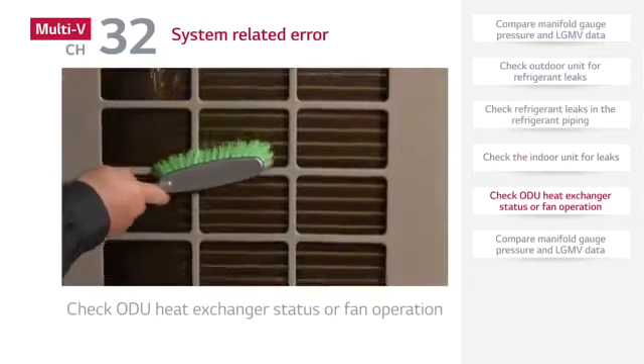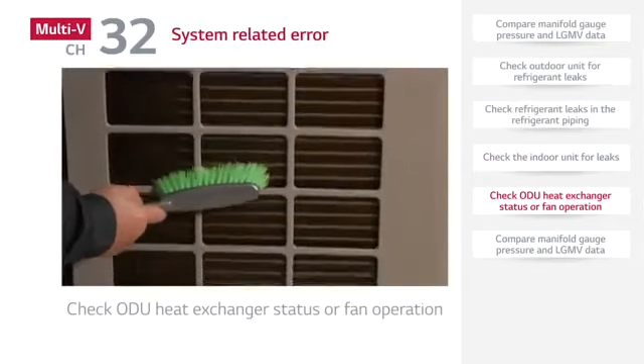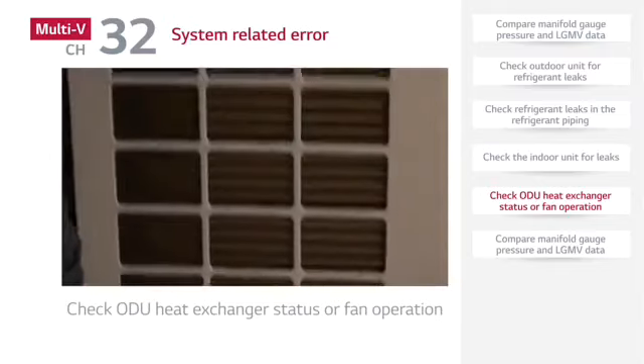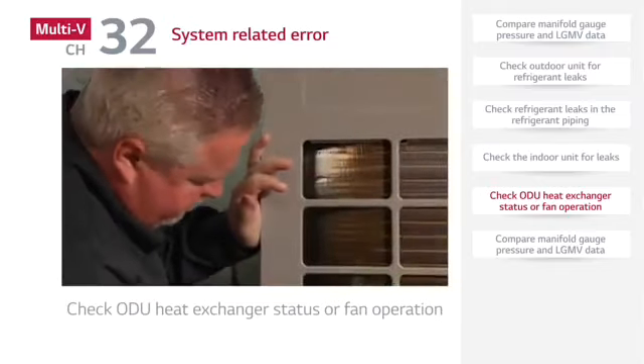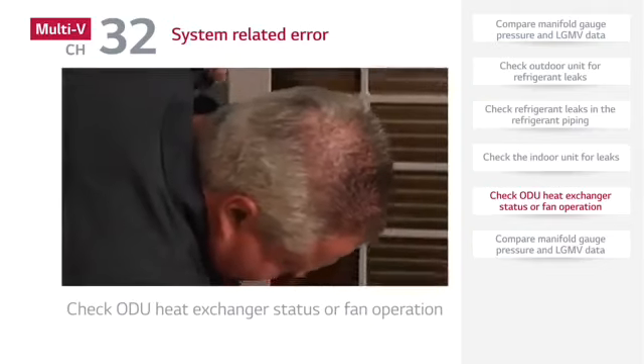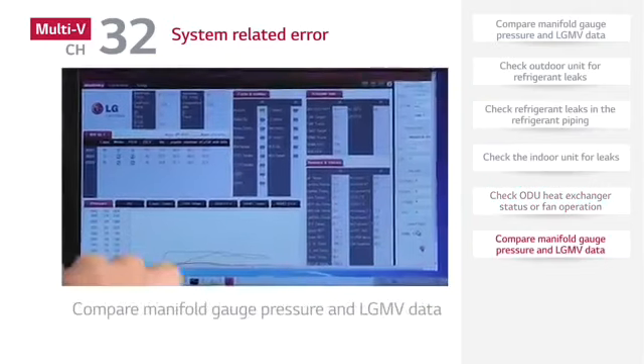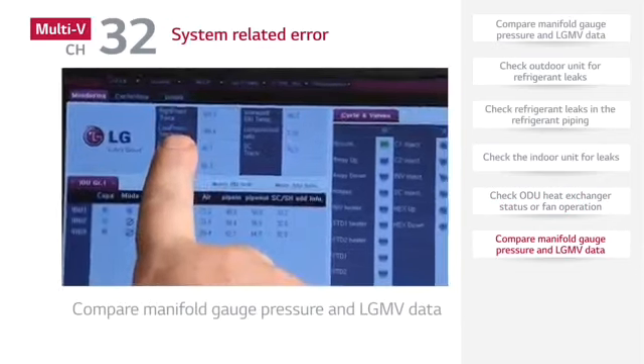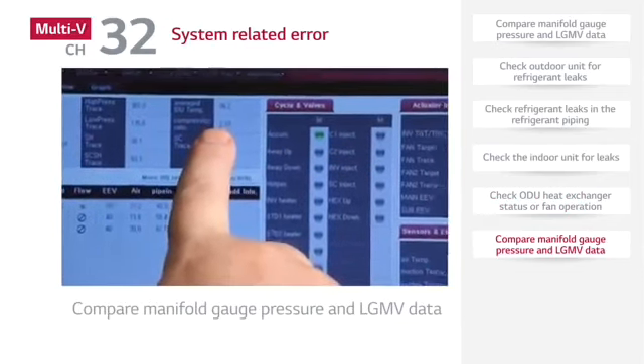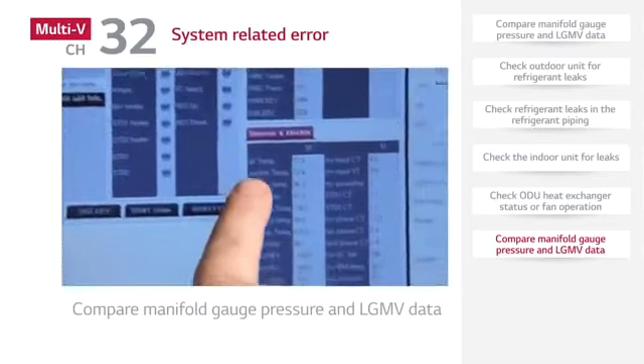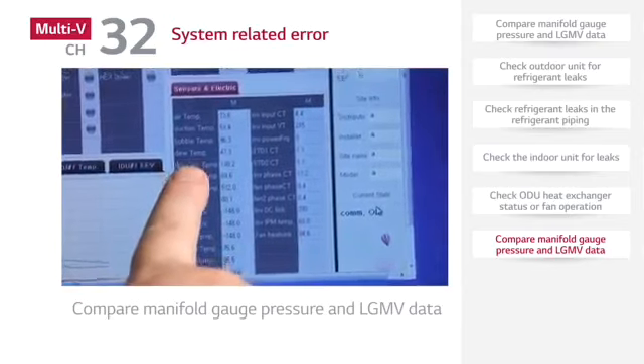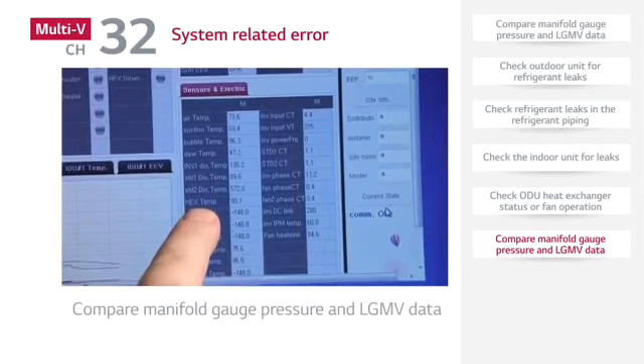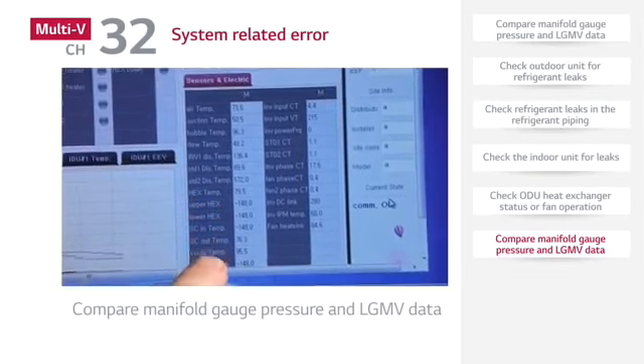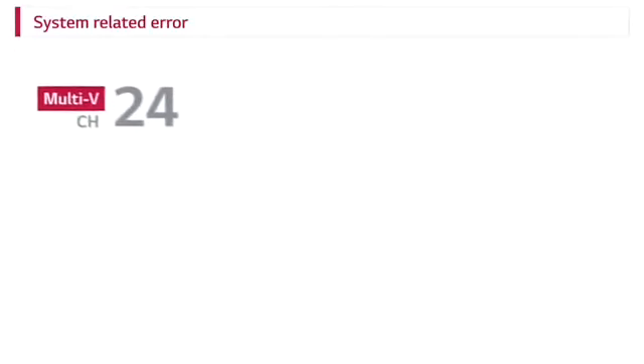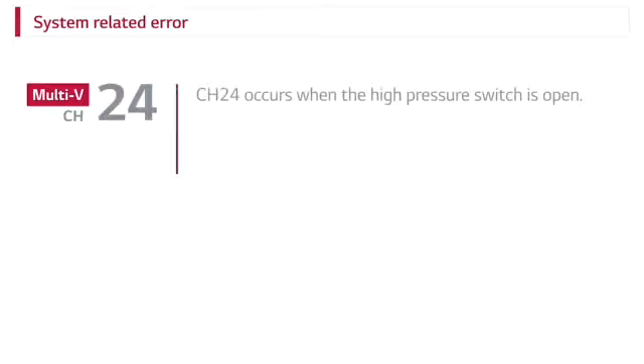After checking indoor unit, check outdoor unit heat exchanger status or fan operation. After inspecting the outdoor heat exchanger and fan operation, check whether the LGMV data is normal. A CH24 error indicates the high pressure switch is opened.